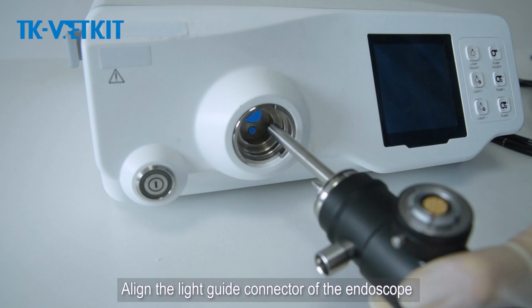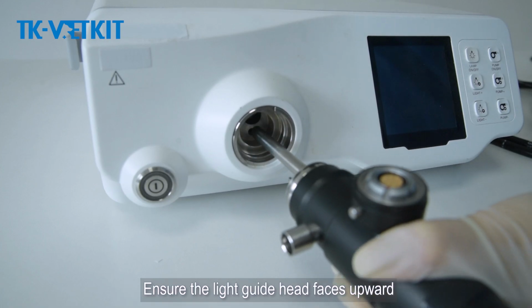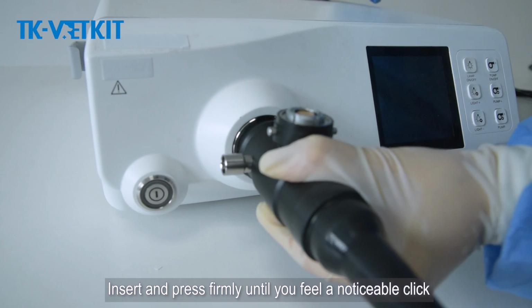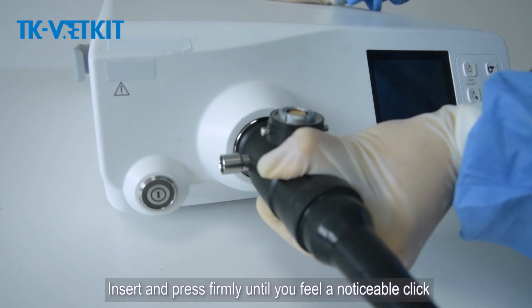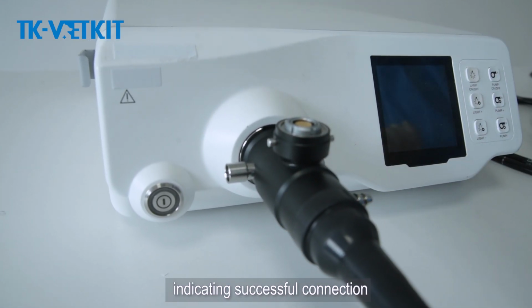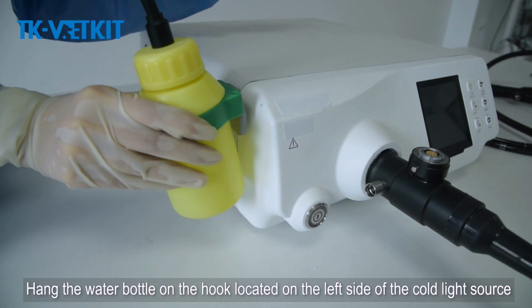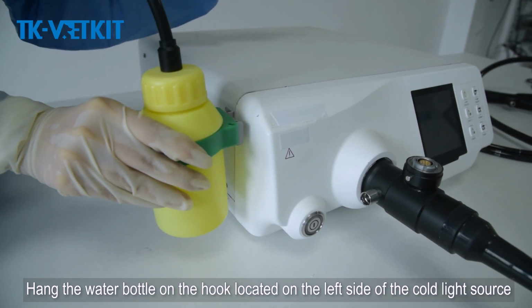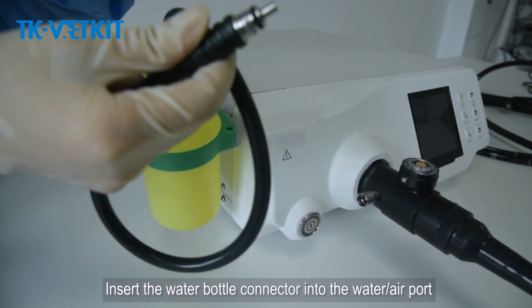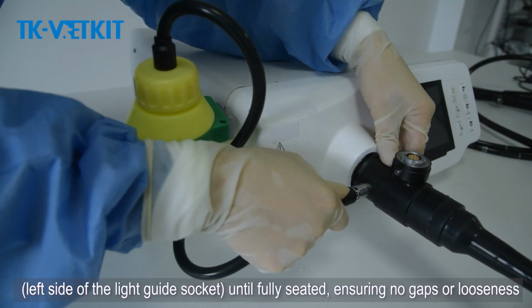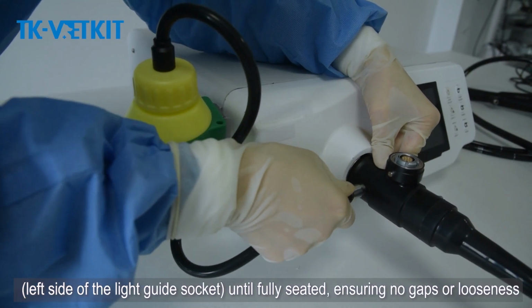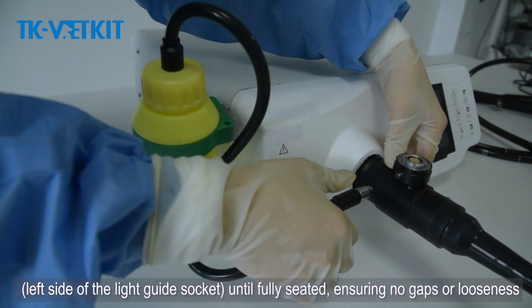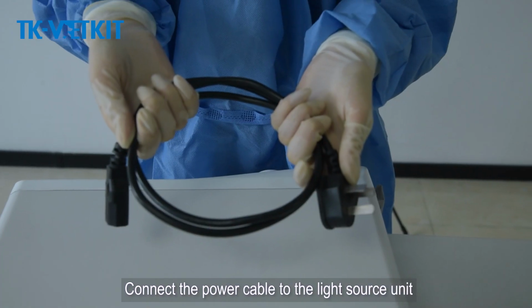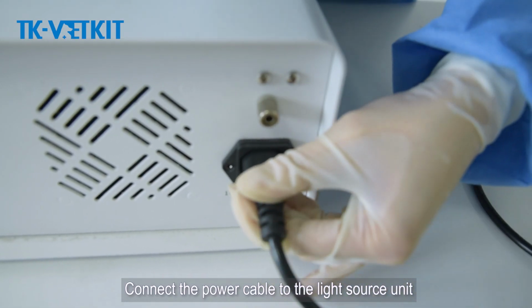Align the light guide connector of the endoscope with the light guide socket on the light source unit. Ensure the light guide head faces upward, insert and press firmly until you feel a noticeable click, indicating successful connection. Hang the water bottle on the hook located on the left side of the cold light source, insert the water bottle connector into the water/air port, left side of the light guide socket, until fully seated, ensuring no gaps or looseness. Connect the power cable to the light source unit.